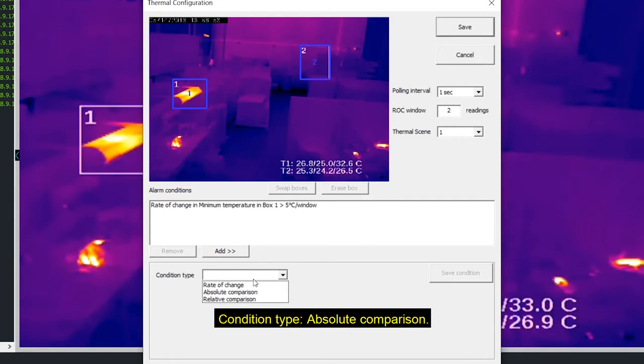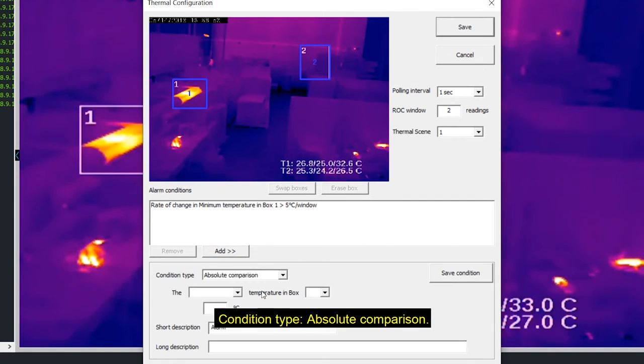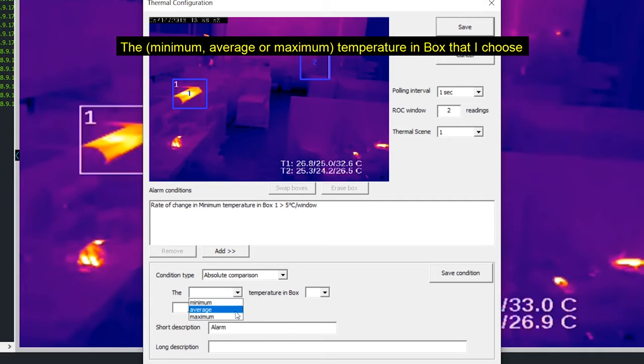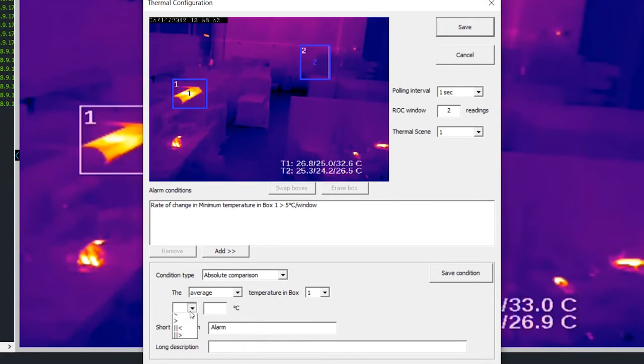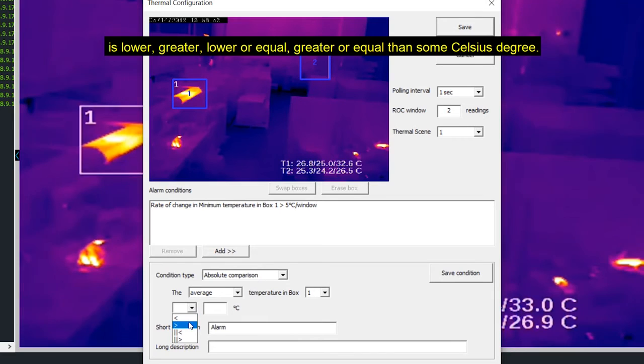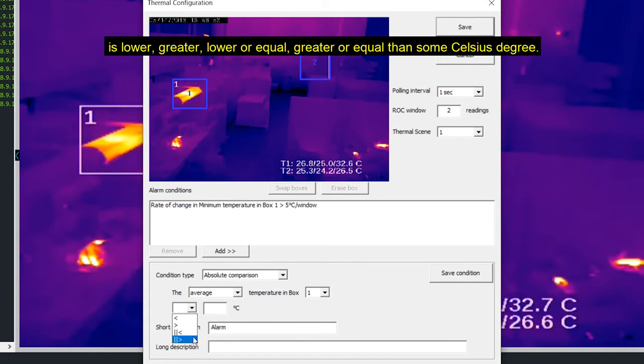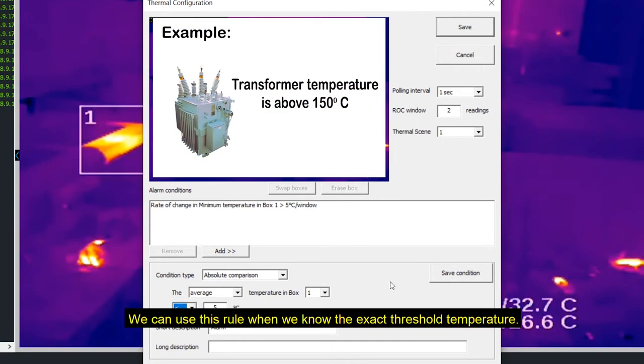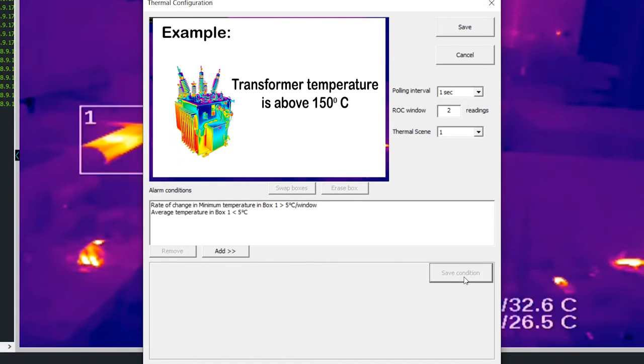Condition type, absolute comparison. The minimum, average or maximum temperature in box that I choose is lower, greater, lower or equal, greater or equal than some Celsius degree. We can use this rule when we know exactly the threshold temperature.